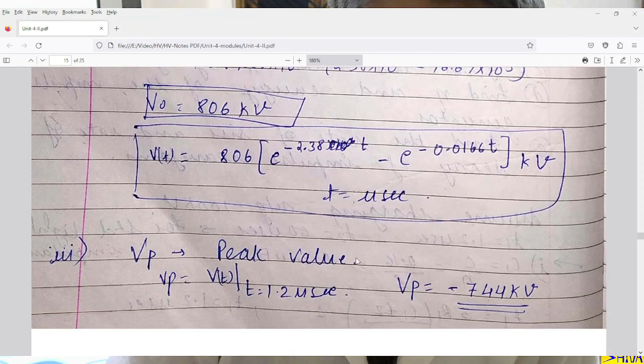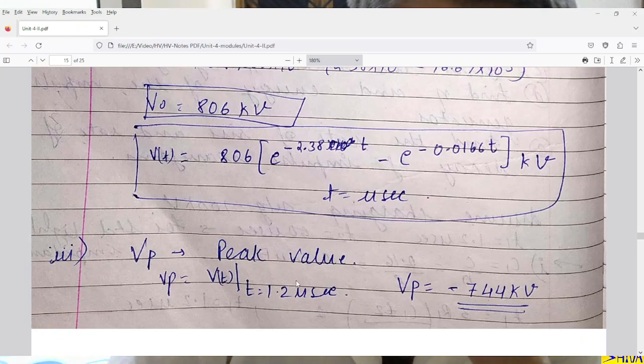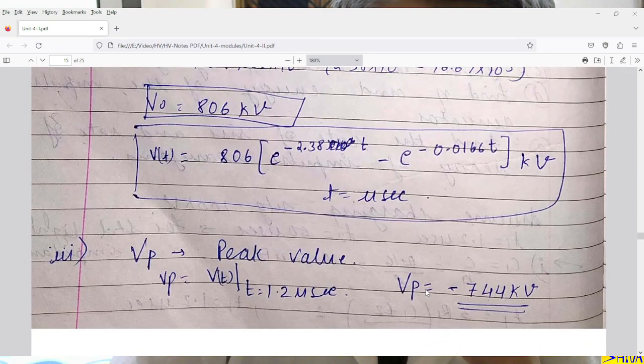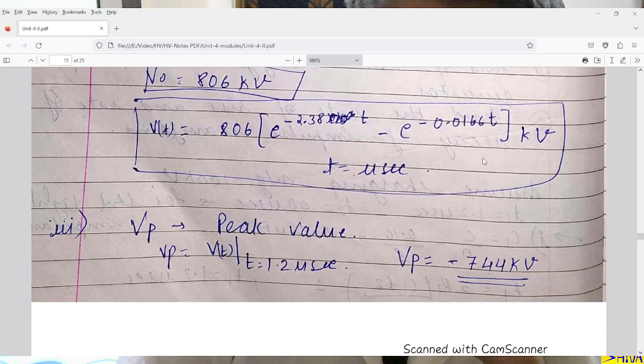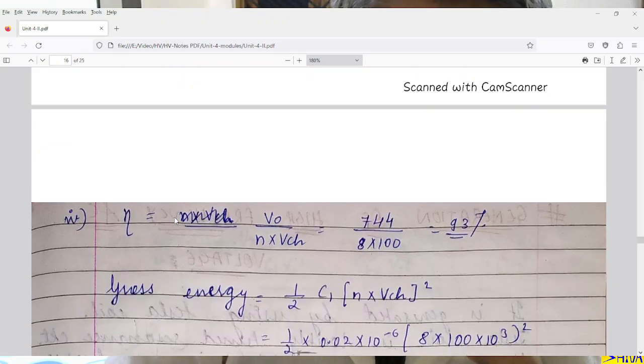The third part requires computing the peak value — the maximum value of the impulse voltage waveform. The maximum value is attained when time equals 1.2 microseconds, so we substitute t = 1.2 into the equation. After computation, the peak value is −744 kV.